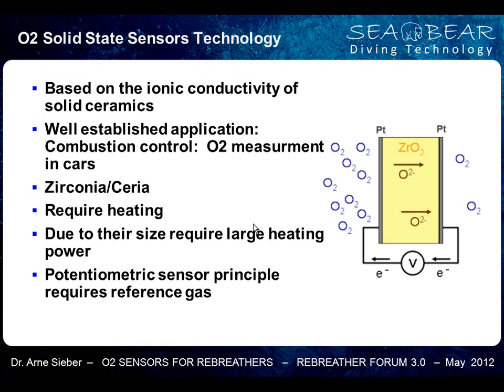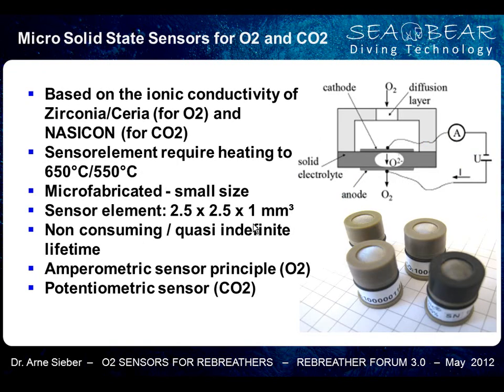Solid state sensor technology is something different. We have been looking into that for the last years. Oxygen sensors in solid state technology are similar to the lambda sensor in your car. It basically works on ceramics that become ion conductive under higher temperatures. There are very small microfabricated sensors with sensing elements of 2.5 by 2.5 millimeters, so they are perfectly suitable for integration into a mouthpiece. There are amperometric sensors for oxygen, but also similar-size sensors for measuring carbon dioxide.